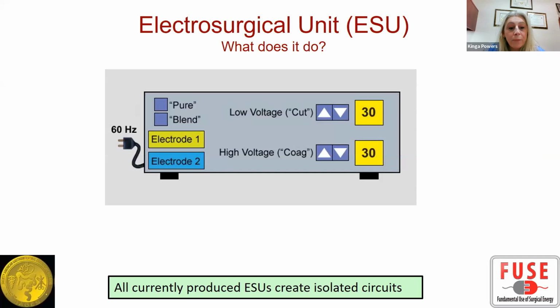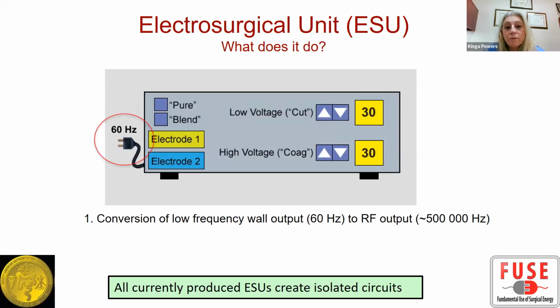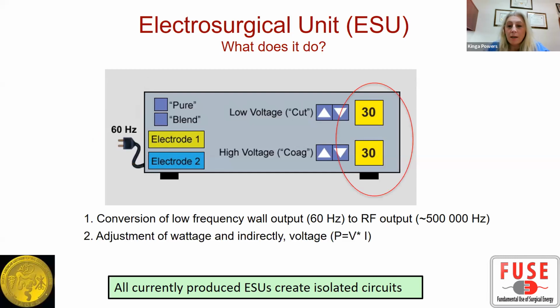The second thing that it does is it allows you to adjust the voltage of the output, something that you do indirectly by adjusting the power. So if you put in the power such as 30 or 20, that's power in watts, which is actually equal to current times voltage. Modern ESUs can sometimes alter the voltage in response to how the tissue responds, the tissue resistance or impedance. But most of the time, the ESUs that we use do not. So we have to be cognizant of what we set our power on, and later we'll talk about the duty cycle. But we usually choose this power in watts, the 20 or 30 watts.